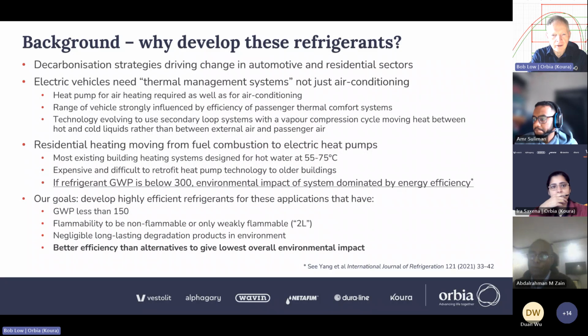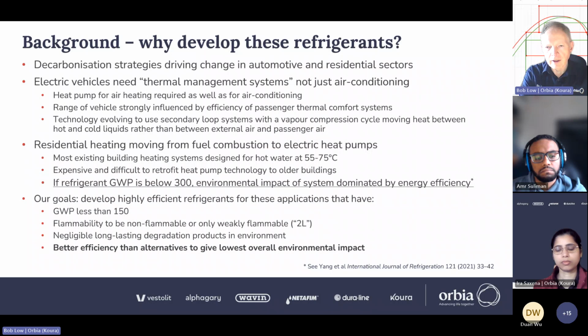And as we look at the total environmental impact of heat pumping, once you drop the GWP of the refrigerant below 300, in fact, the environmental impact is dominated by energy efficiency, completely dominated. There's a rather good analysis of this in the International Journal of Refrigeration from a few years ago, which shows how you'd arrive at that conclusion quite nicely. So if you have a lot of heat pumps, even a 5% gain over the fleet is a significant gain in environmental impact.